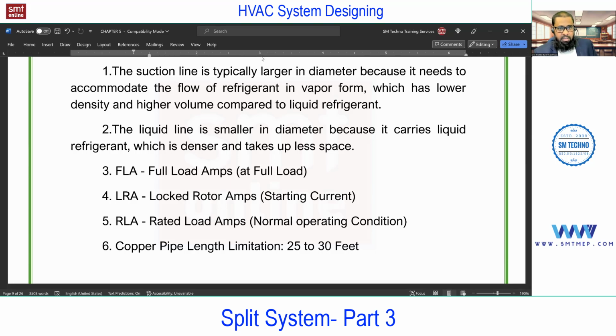Remember FLA. In short, we call it FLA. It's full load ampere. So what is full load ampere? Remember, when the compressor is running at full load, the current drawn by the compressor is called FLA. Simple. Next is LRA, locked rotor ampere, nothing but starting current. And remember, LRA is always more than FLA. So what exactly is LRA? I think you can notice when you switch on the refrigerator or the AC, for a few seconds you'll find a fluctuation because the starting current is high. Why is the starting current high? Because the compressor is in the locked state.